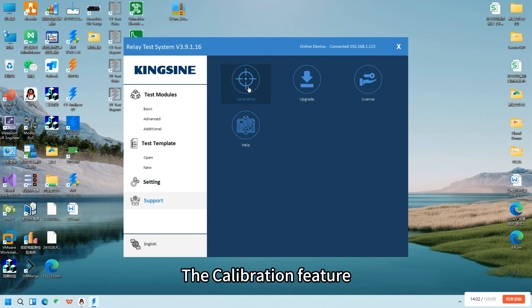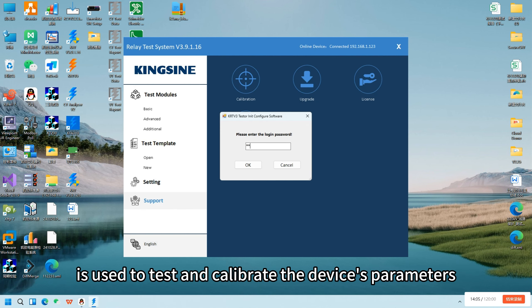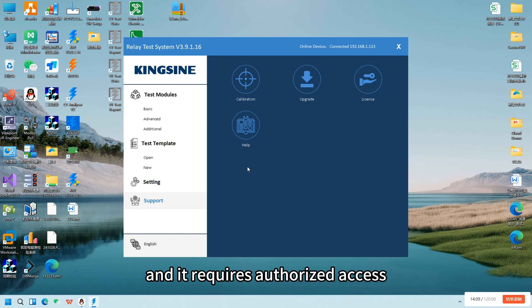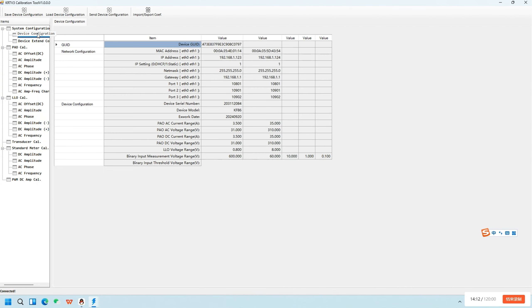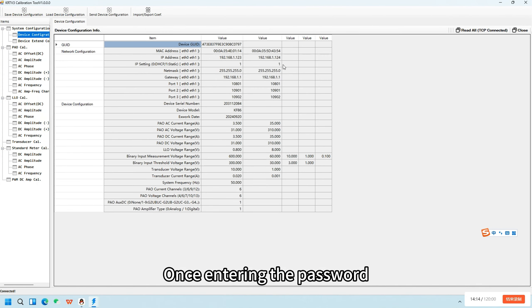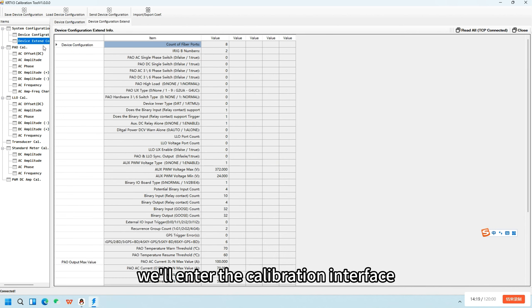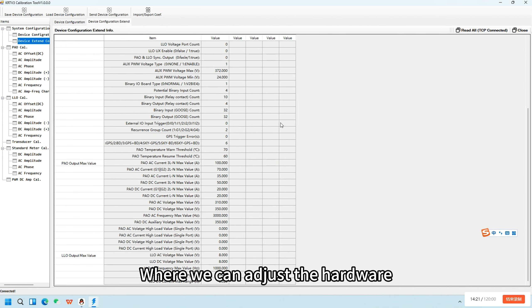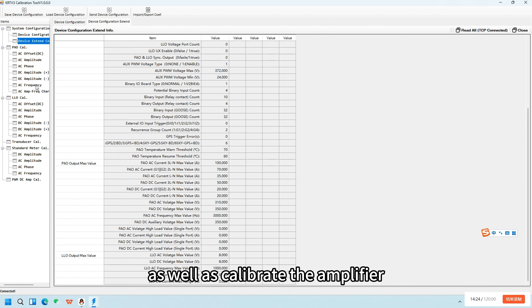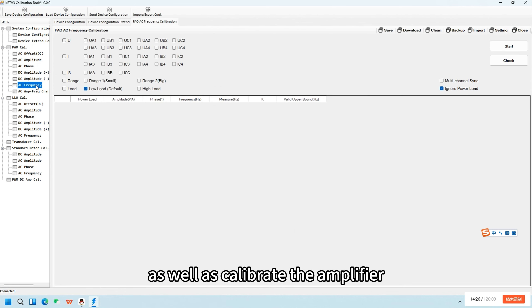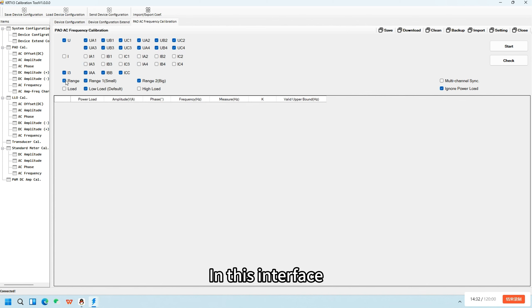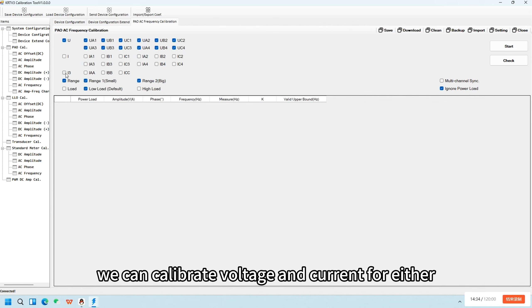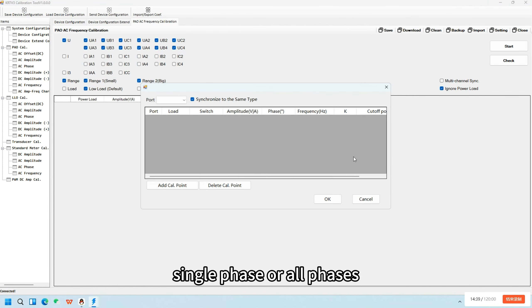The calibration feature is used to test and calibrate the device's parameters and requires authorized access. Once entering the password, we'll enter the calibration interface where we can adjust the hardware settings of the tester as well as calibrate the amplifier and low-level outputs. In this interface, we can calibrate voltage and current for either single phase or all phases.